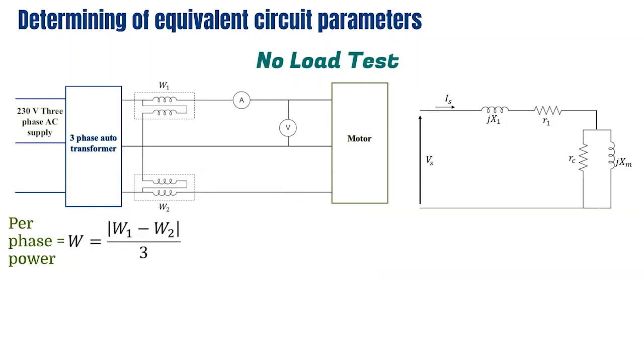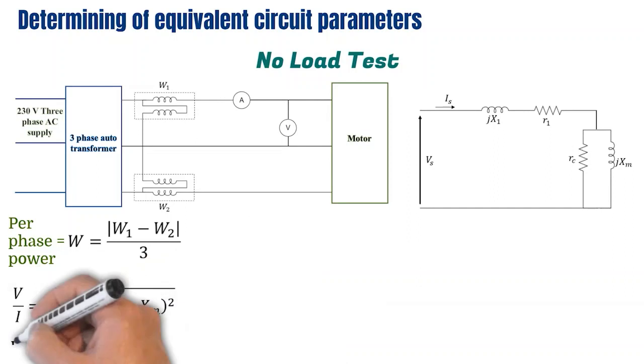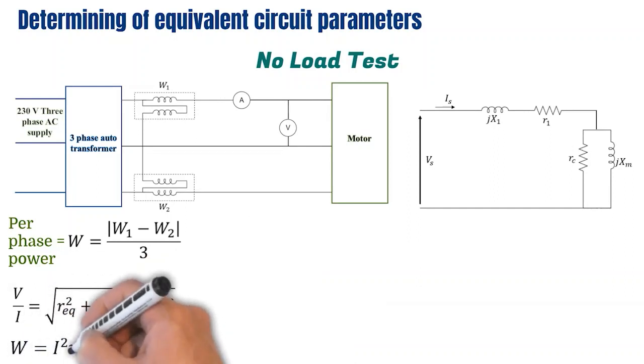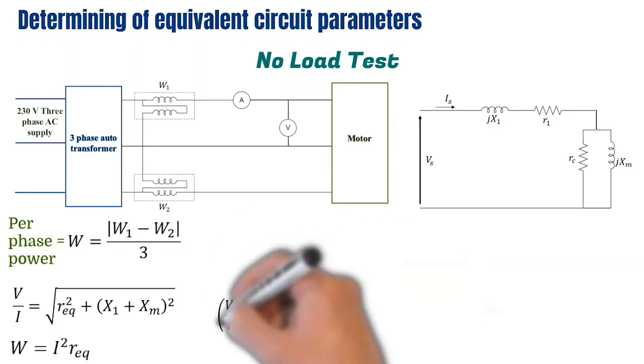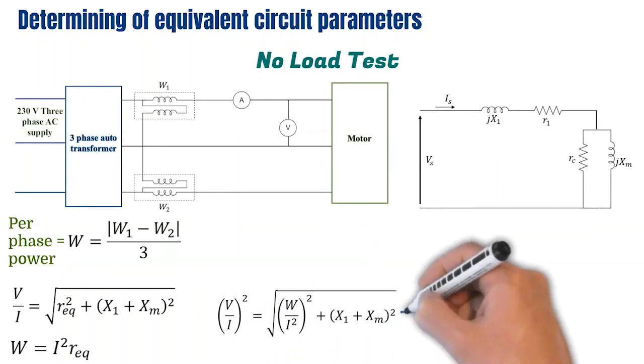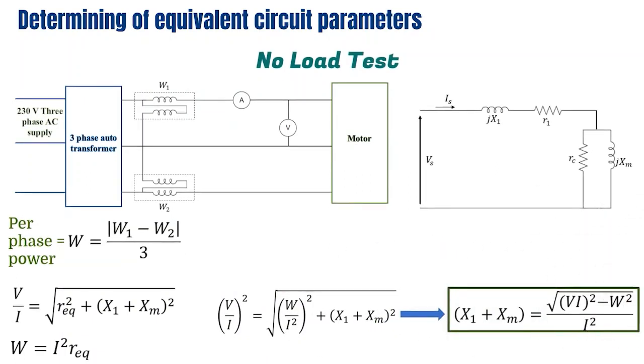Observing the simplified no-load circuit, we can write an equation where R_eq is the resultant resistance responsible for producing the wattmeter power W, I is the ammeter reading, and V is the per-phase voltage obtained by dividing the voltmeter reading by root 3. Finally, with these equations we can derive an expression for X1 plus Xm.